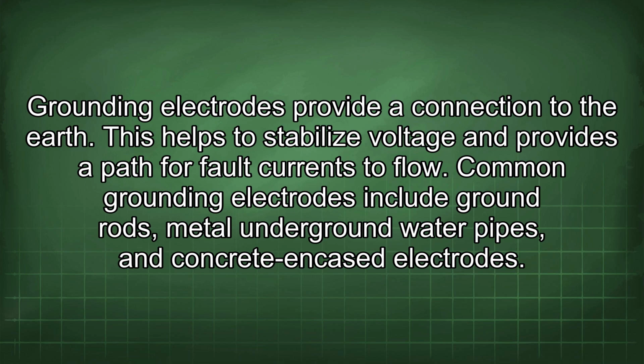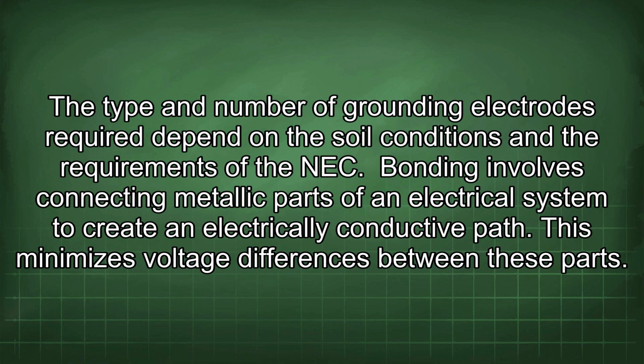Grounding electrodes provide a connection to the earth. This helps to stabilize voltage and provides a path for fault currents to flow. Common grounding electrodes include ground rods, metal underground water pipes, and concrete encased electrodes. The type and number of grounding electrodes required depend on the soil conditions and the requirements of the NEC.